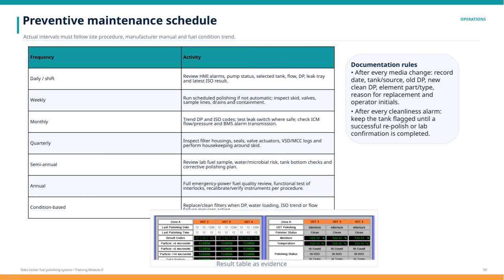trending differential pressure and ISO codes is crucial, along with testing the leak switch if it's safe to do so, and checking flow, pressure, and alarm transmissions to the BMS. Quarterly maintenance focuses on inspecting filter housings, seals, valve actuators, as well as reviewing VSD and MCC logs, and performing housekeeping around the skid. Every 6 months, a review of lab fuel samples, evaluation of water and microbial risks, tank bottom inspections, and updating the corrective polishing plan are necessary. Annually, there should be a comprehensive review of emergency power fuel quality, functional tests of interlocks, and recalibration or verification of instruments according to procedure.